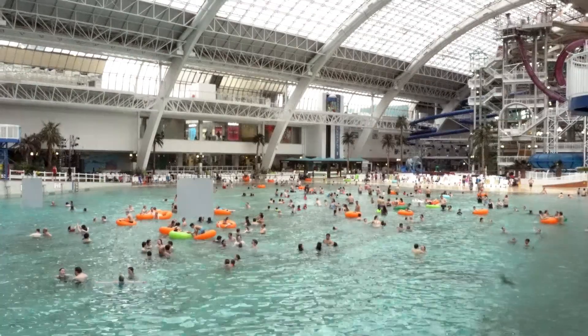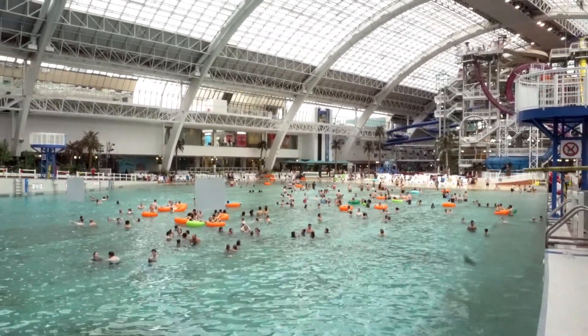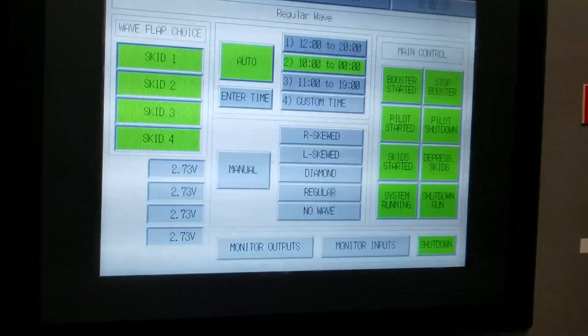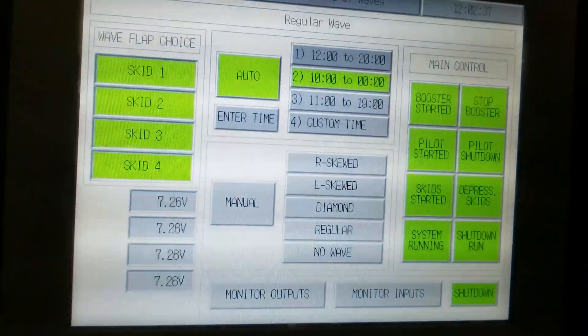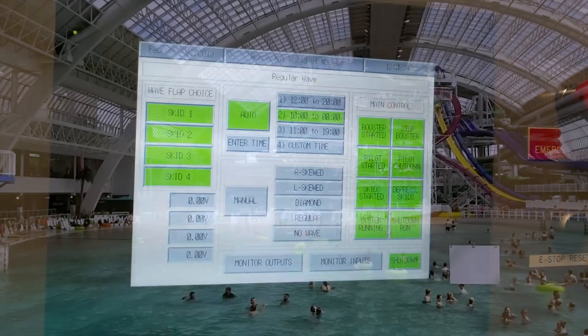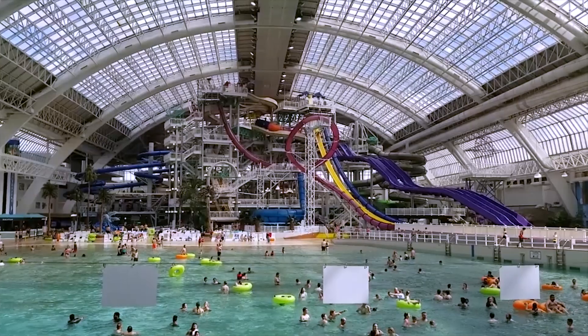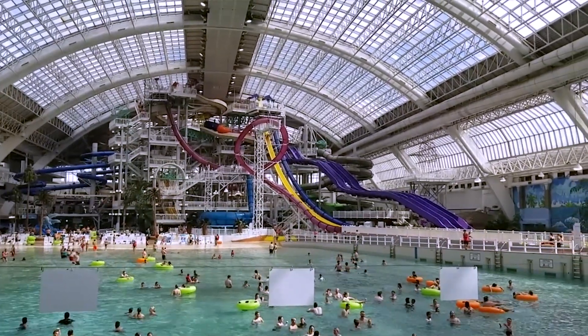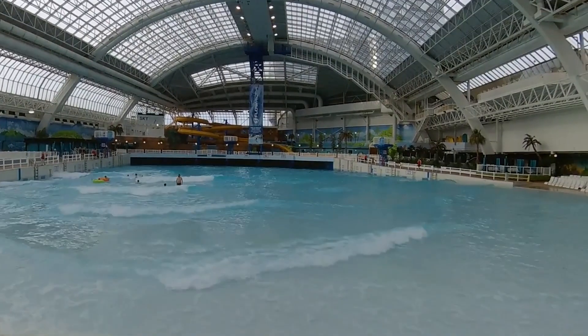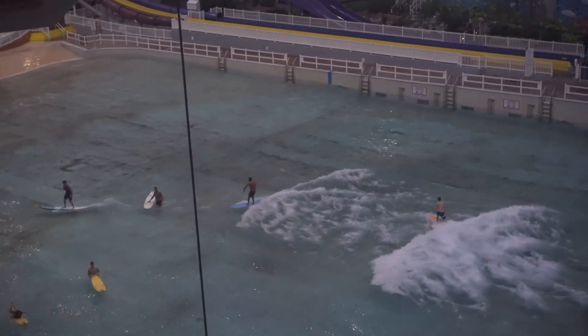While some of the more extreme among us might be a little disappointed that the 12-panel system has been scaled back, the remaining eight panels can still dish out some pretty impressive waves. Today's control system allows for the customization of wave pattern and intensity — there's more than enough power to supply intense waves for surfing, kayaking, and more. The typical pattern is a set of five waves followed by a few seconds' delay before another set is pushed out. This pattern is typically run for 10 minutes on and 5 minutes off, allowing the system to cool down and giving lifeguards a break. But the pattern and timing can be changed for special events like surfing, where the five-wave pattern is run continuously.